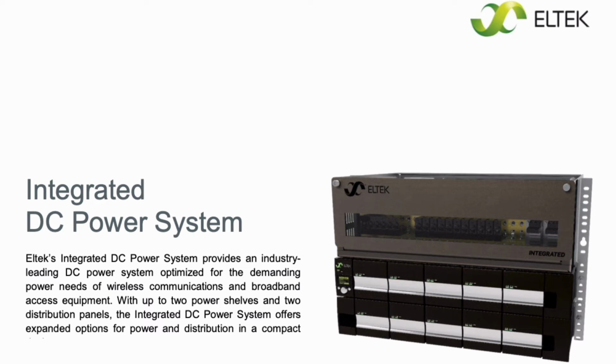For n+1 redundancy, 9 devices are needed. This means the plant picked must be at least 9 times 50, or 450 amps or greater in size. The integrated family from Eltek, now Delta, will work fine for this.